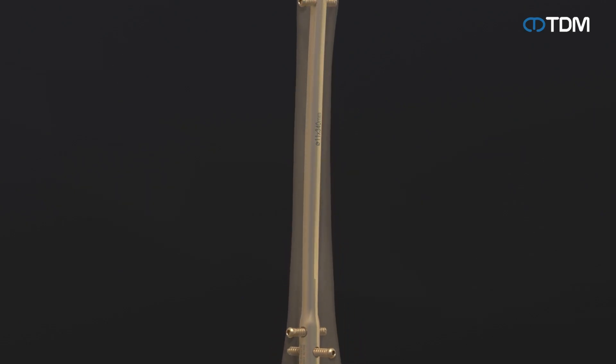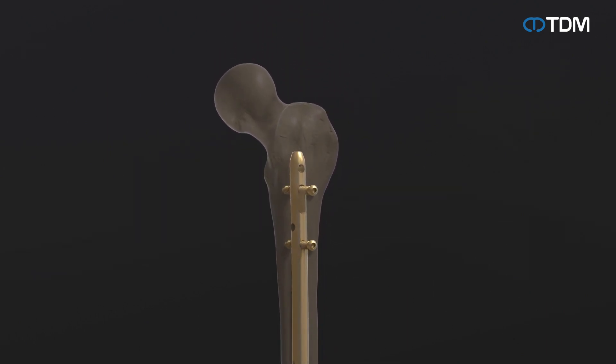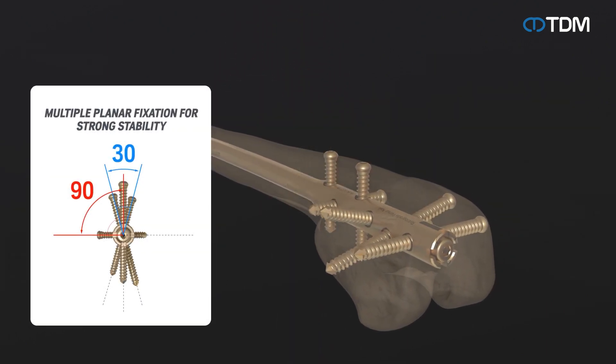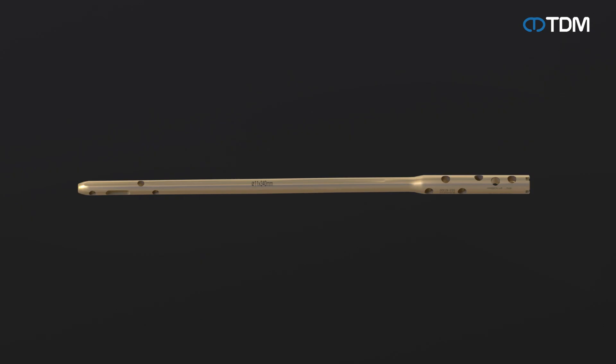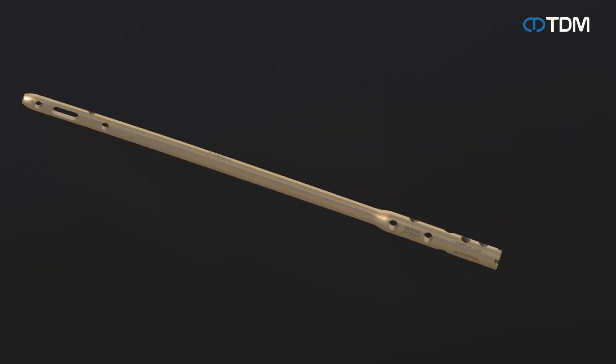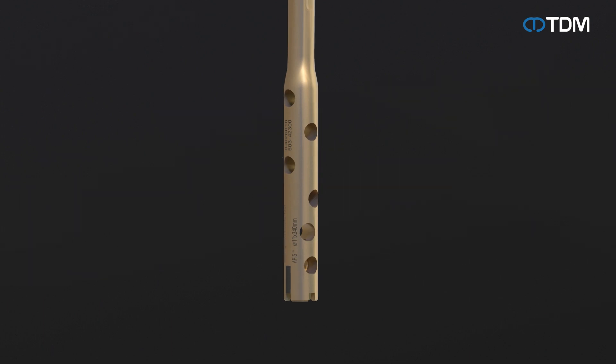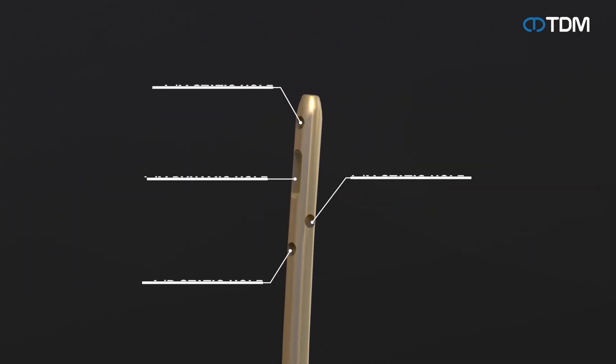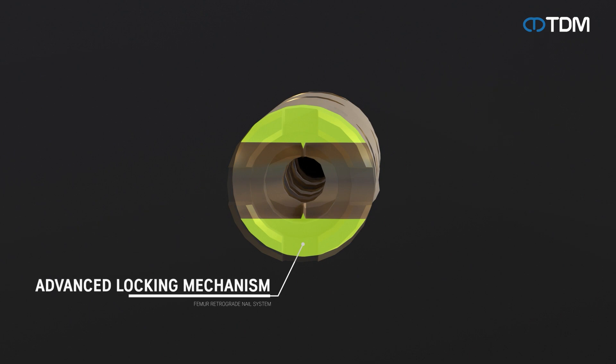The femur retrograde nail system is used for cases such as femoral shaft fractures, multiple fractures, and fractures after arthroplasty. The nail is made of titanium alloy and has a bending shape to match the shape of the femur. It consists of six distal screw holes and four proximal screw holes. The screw hole is a semi-locking hole mechanism to prevent loosening, enabling more stable treatment.